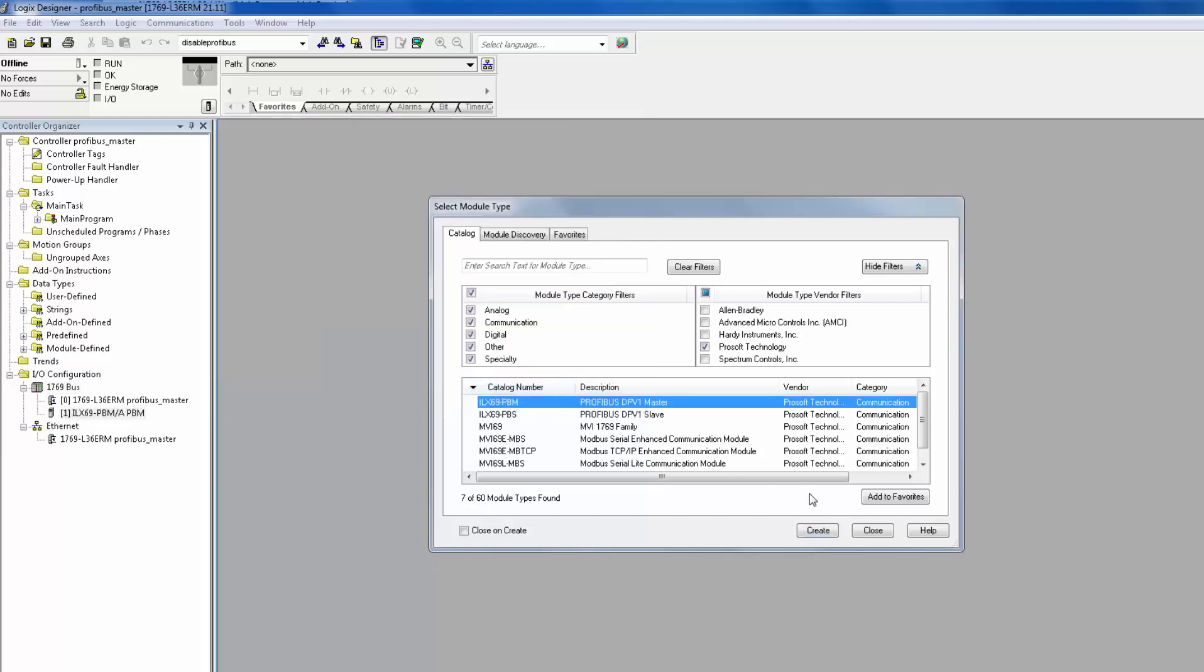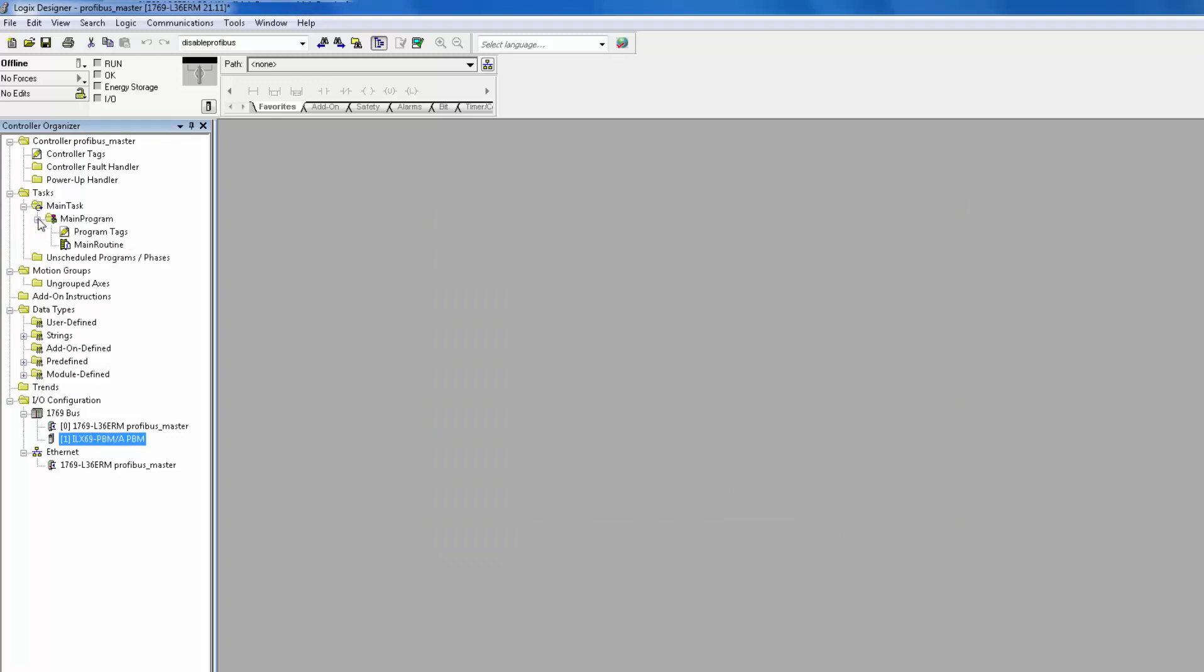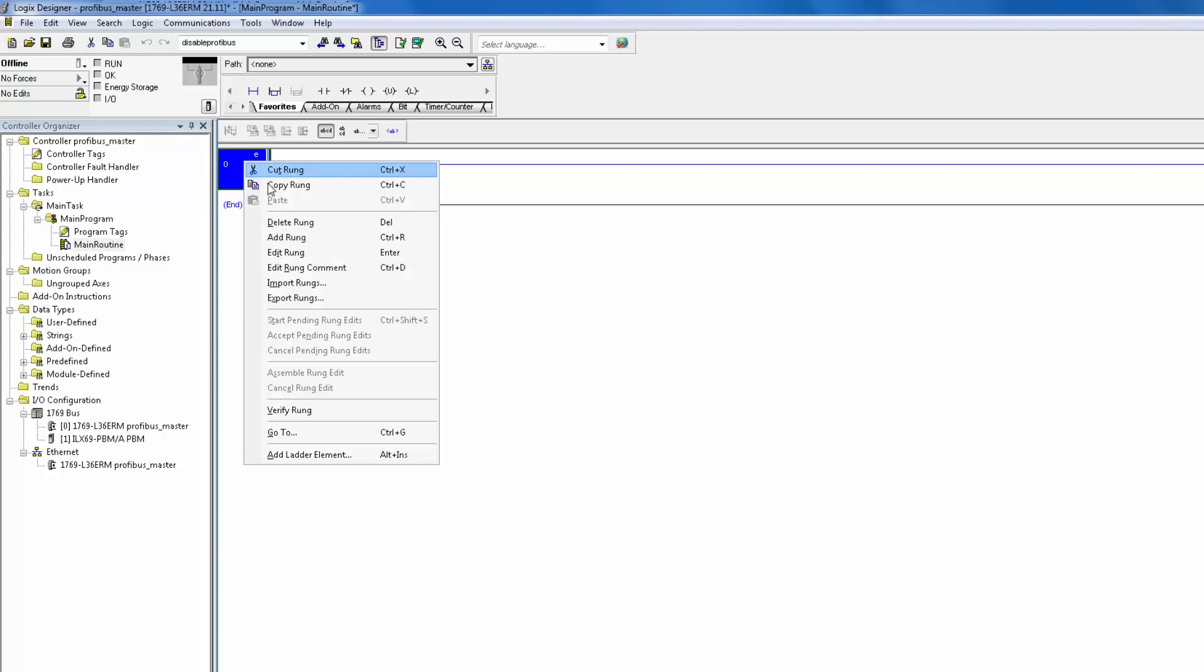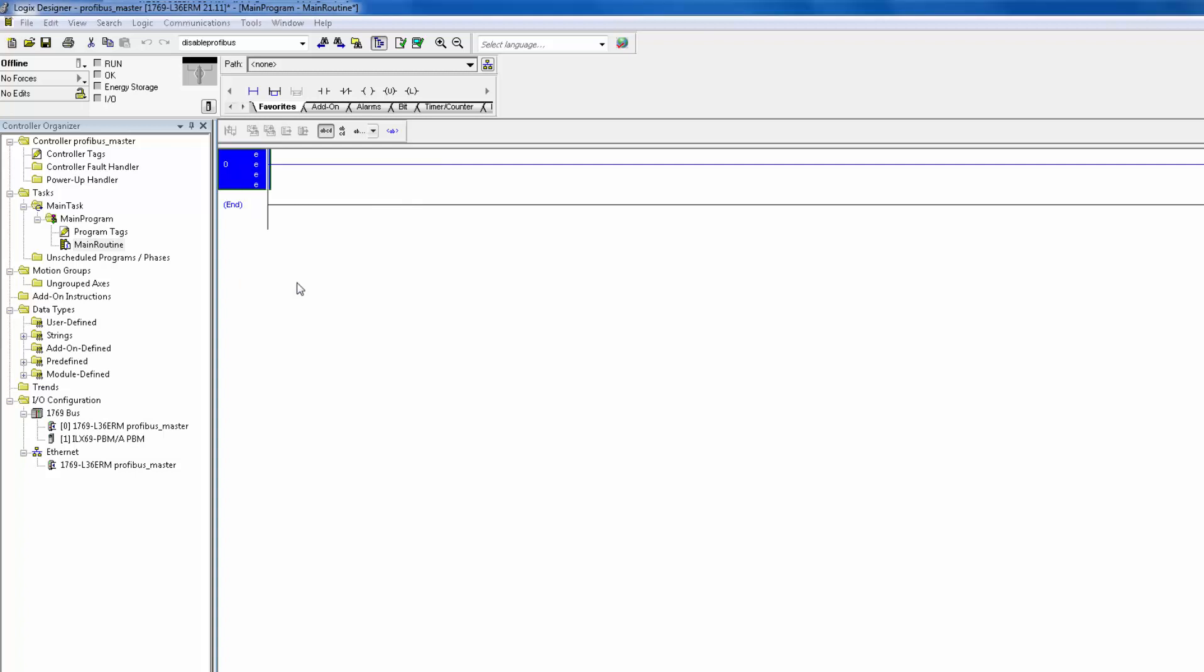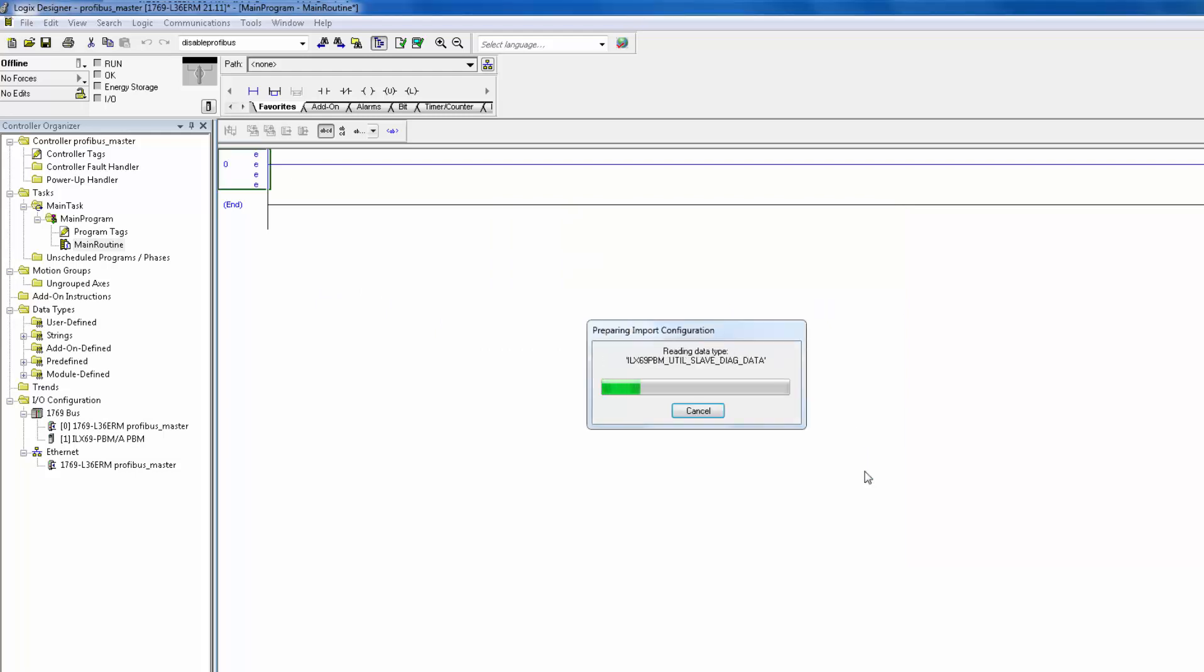Now we need to install the add-on instruction to get this module talking to the processor and bring in some diagnostic data. Double-click on the main routine. If you do not wish to install this in the main routine, it is OK. Just make sure that routine is being called by the main routine. Right-click on any rung and click Import Rungs. Choose the ILX69 PBM AOI. This can be found on the DVD shipped with the module or from our website. Then click Import.